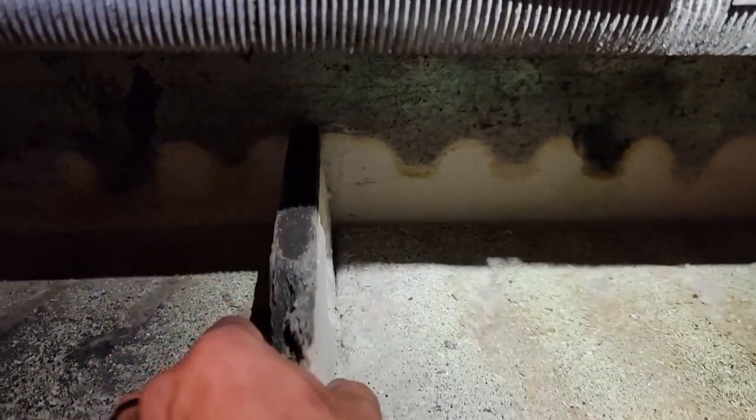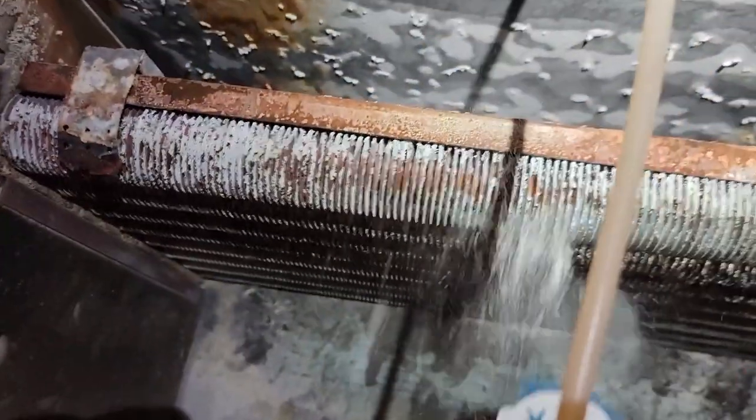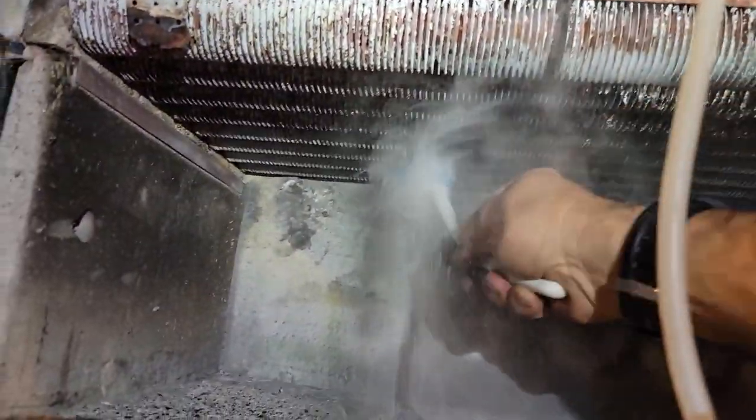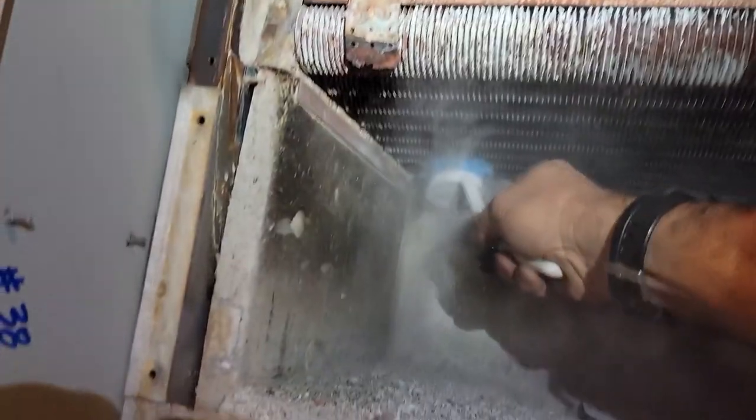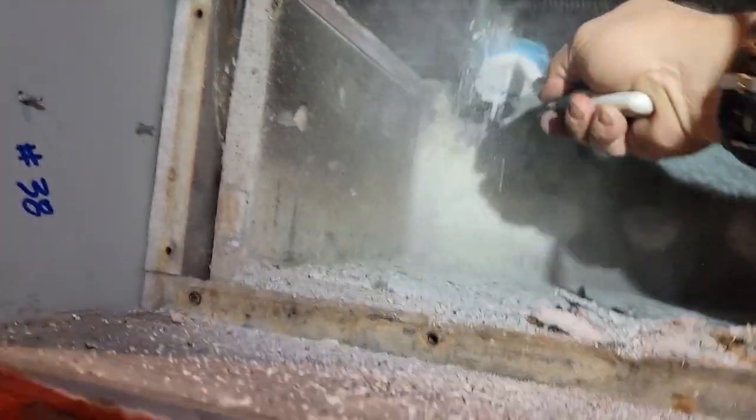Looks like it should come right out. I don't really recommend hitting with anything hard like a true hard wire brush. You want to make sure this doesn't get disturbed. Let's get this thing cleaned out. I got a brush out there I use. Oh yeah, look at that, I can see that causing a little bit of problems with our CO levels.